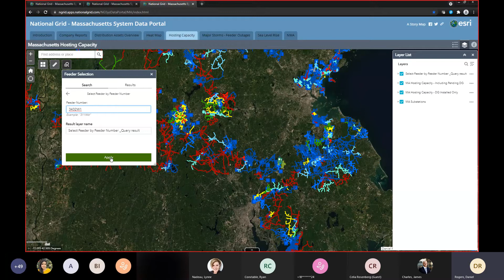So the current available hosting capacity is 6.65 megawatts. And this is taking into account connected DG, which there is one small rooftop, it looks like. It is so high though, because if you look, there's only 350 kilowatts connected. So there's no ongoing or potential for an ASO. This was updated recently.